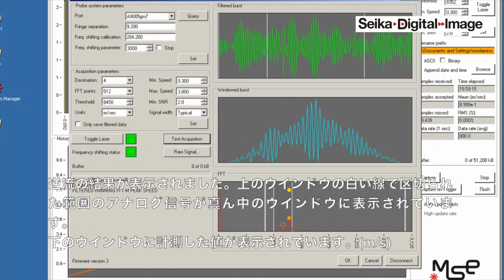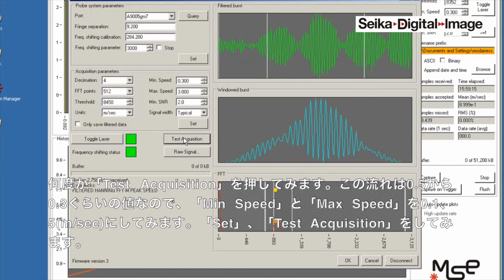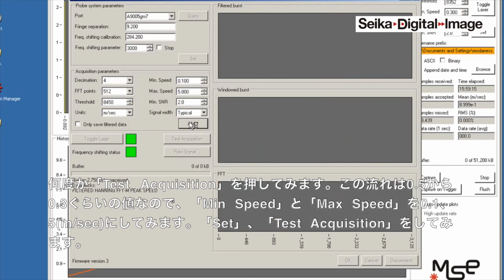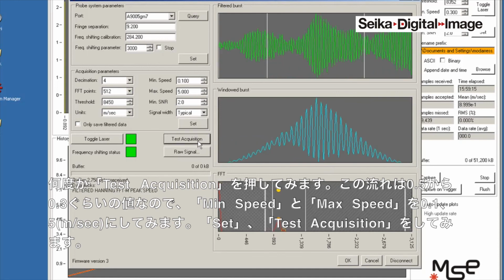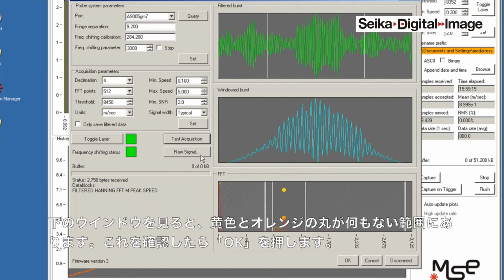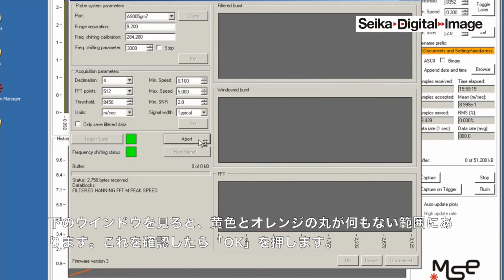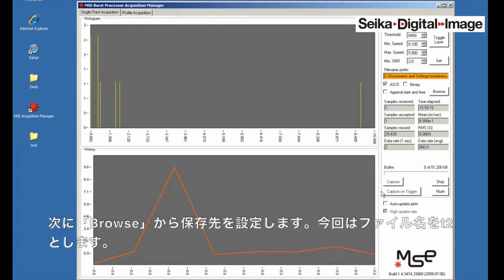What it does is provide you the shifted frequency signal, again the processed analog signal between these two limits, and then the value of the measurement in meters per second. In this case, for this flow, it goes from 0.5 to 0.3. So maybe we want to open up here, let's say 0.1 to 5 meters per second, in order not to limit our measurement. Now you can take a few samples and look at the scope here and see that your signal is in the clear area, which is the band defined by your band pass filter. And you push OK and capture a signal.